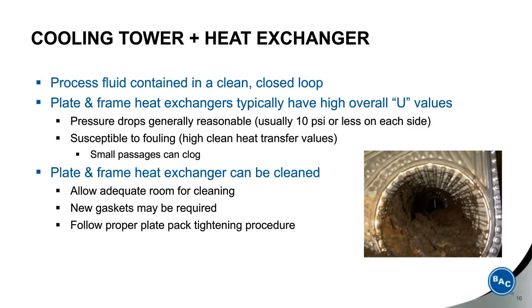You need to allow adequate room in the equipment room for this cleaning. We also suggest you have a drain available nearby, because when you take the plate pack apart, you're going to get some water out of it, and you're going to be cleaning the plates. You also should have new gaskets available should you need them when you're putting the plate pack back together, and you should follow proper plate pack tightening procedures. If you over-tighten, you can have pressure drop issues as well as performance issues, because you need to maintain the proper spacing between each plate.